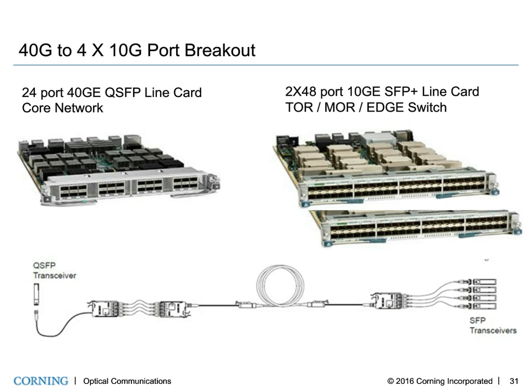40 gig transceivers, as we talked about, were essentially just a series of 10 gig links in parallel. Well, in the software, you could operate those independent channels as 4 10 gig signals, which essentially meant you could take that MTP interface and within the cabling, break that 1 MTP down into 4 LC duplex. And so you could have 40 gig optics on one side of your system and 10 gig optics on the other side of the system. And it turned out this was how you could solve the 10 gig density issue.